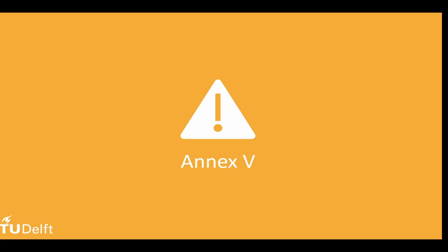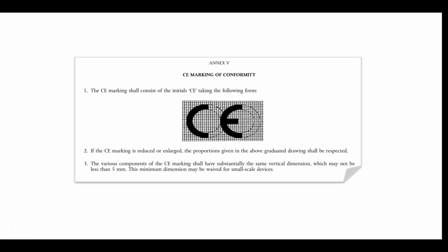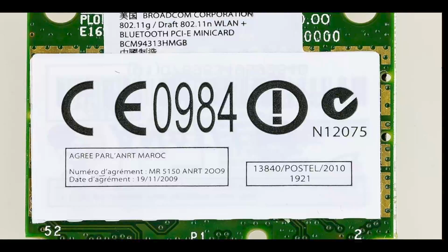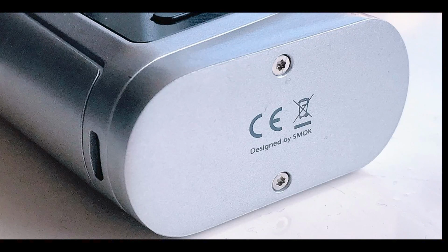But be aware, the CE mark cannot just be the letters C and E in an arbitrary font. It must adhere to the shape and size dictated in MDR Annex 5, and on a product or package that would look like this, or maybe like this. Well, that all looks quite simple, right?